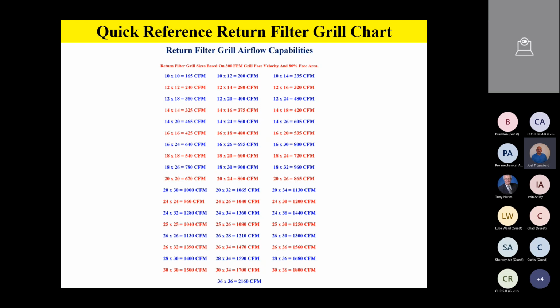So according to Manual D, if that return filter grill has a filter in it, you're going to have a maximum of 300 feet per minute grill face velocity. That's what Manual D recommends. In addition, unless you have some special grills that are made of wood, those are very, very inefficient. They're only about 25 to 40% efficient. If you have some real high-end grills, they might be as high as 95% efficient, what we call free area. But your standard return grills typically are about 80% efficient as far as the amount of air that will actually move through that grill.